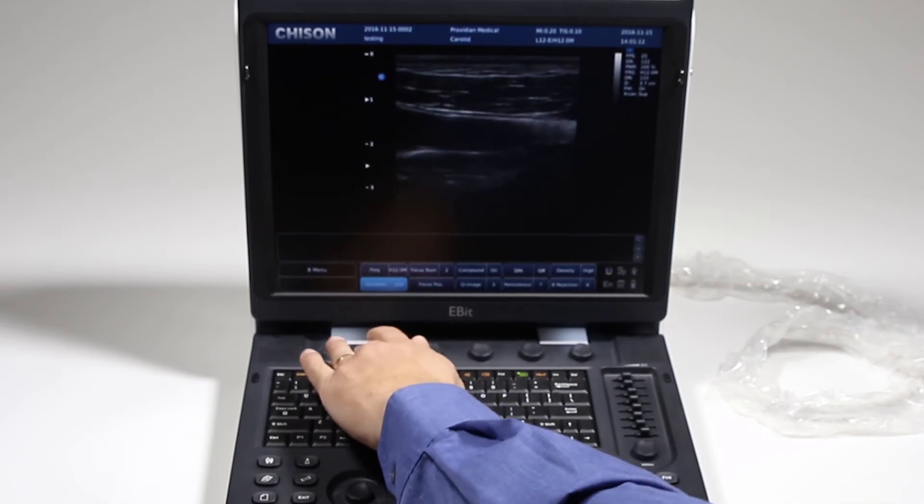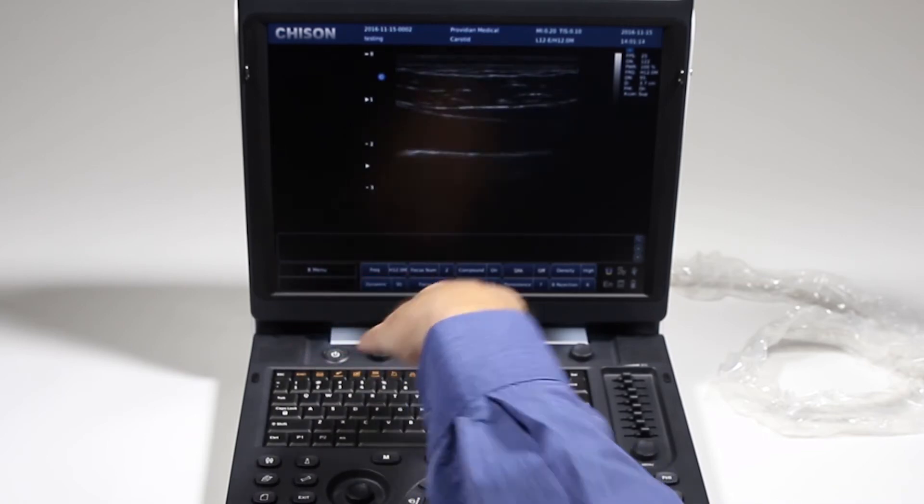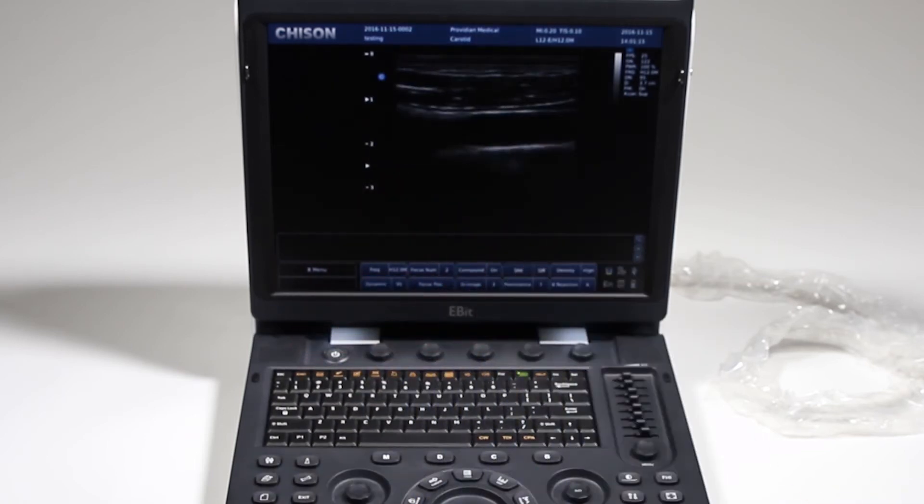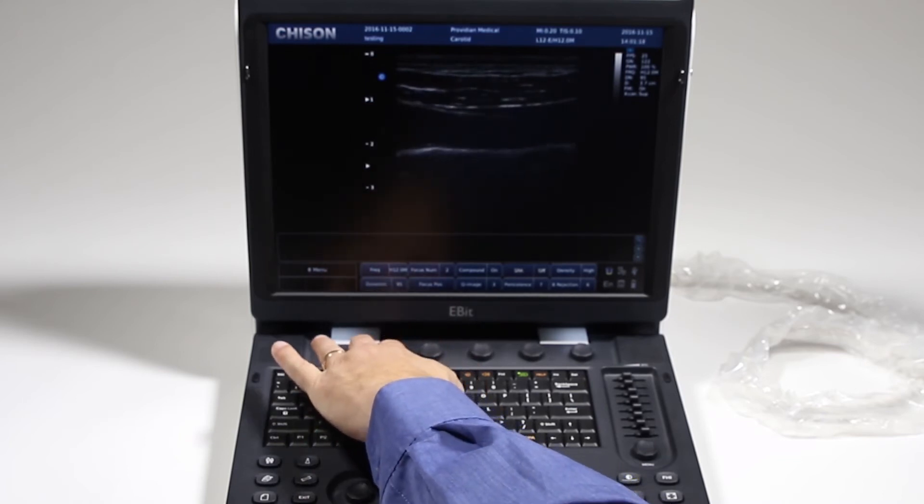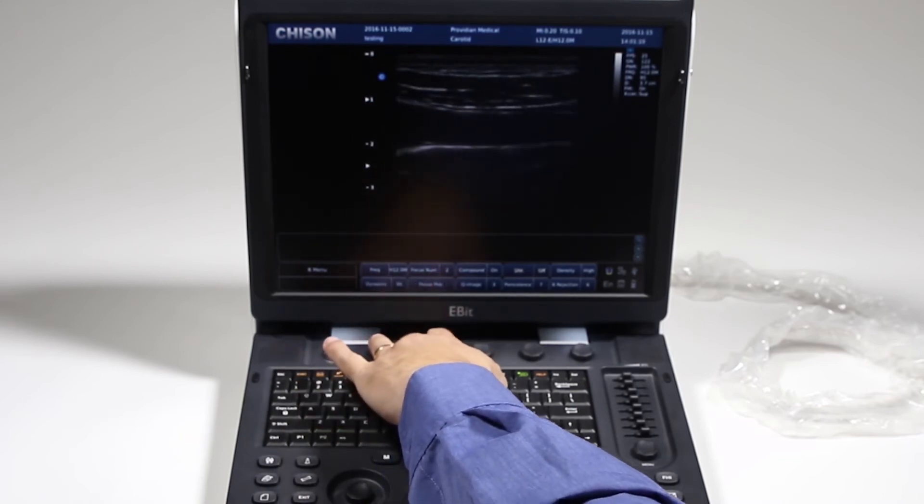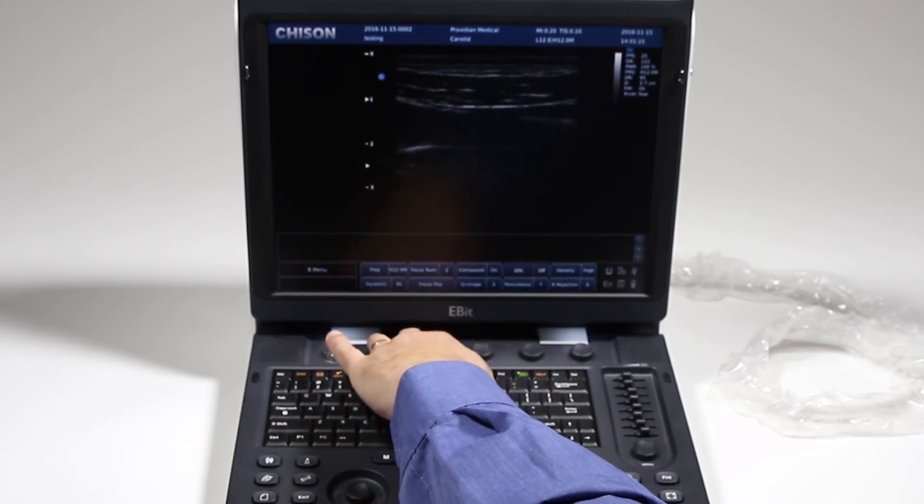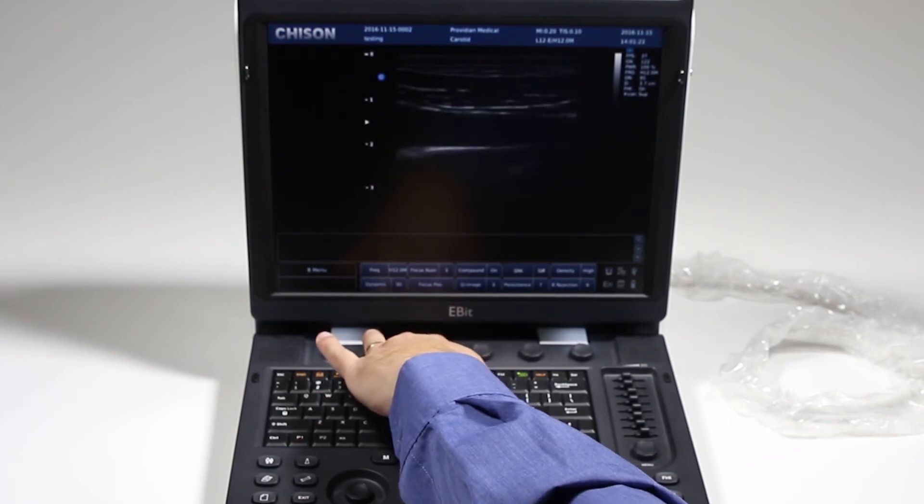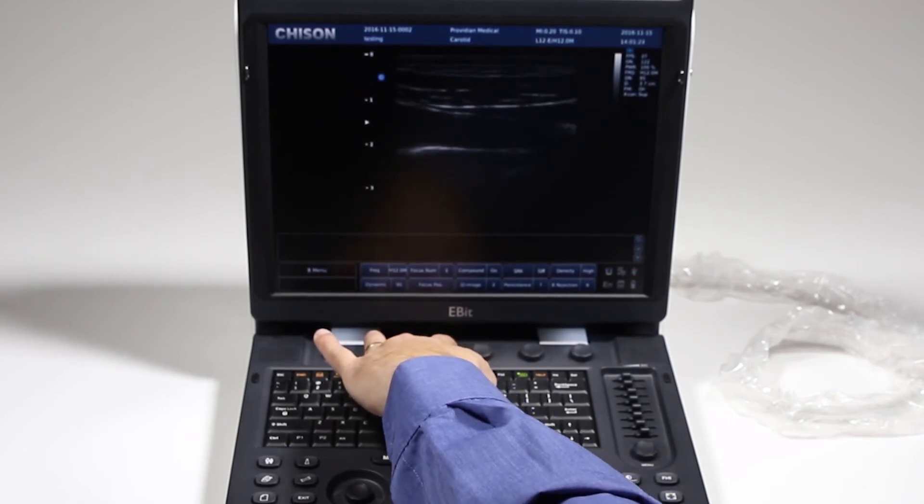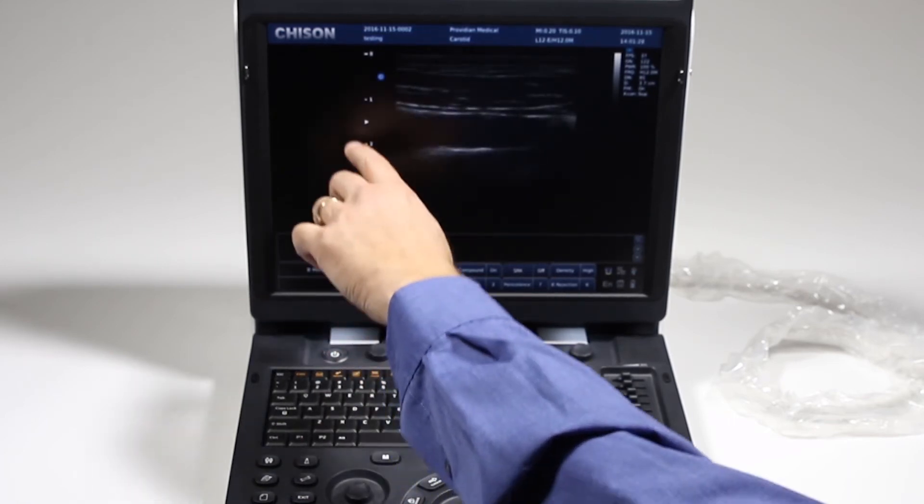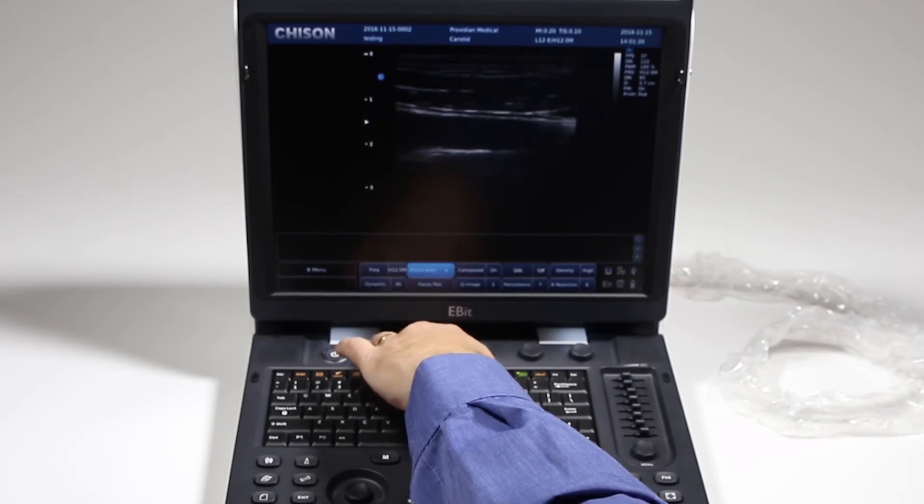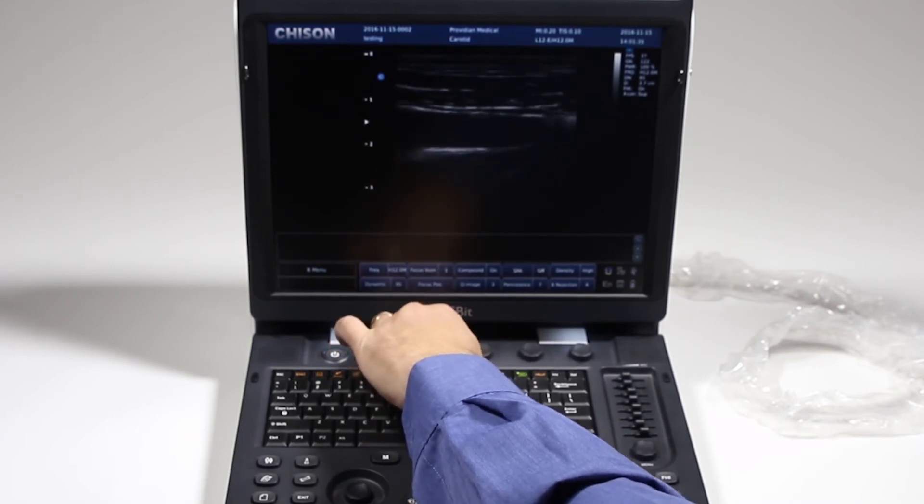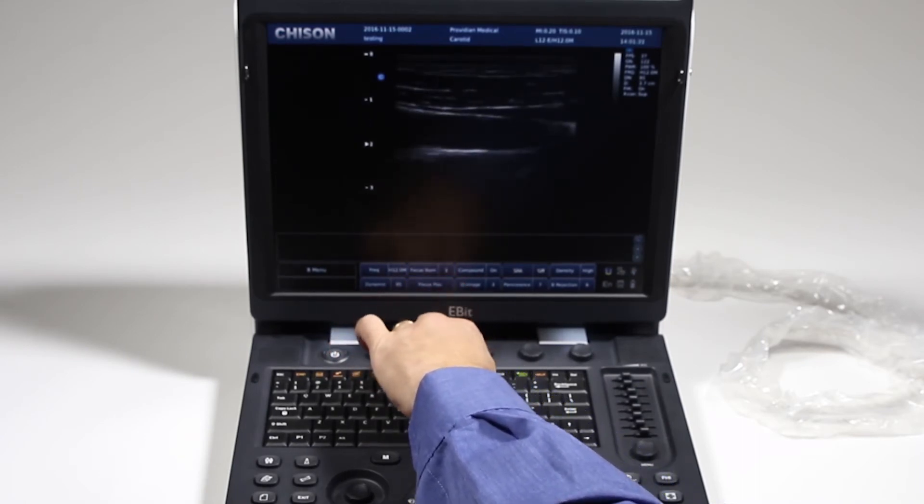The presets are pretty good here, but if you're trying to optimize your image to the best, I'd start with dynamic range and frequency. Also get your focal number and focal position. By reducing the focal numbers, you will increase your frame rate and get a better image in this exact spot here. I can do that and then twist it and adjust my focal position as well.